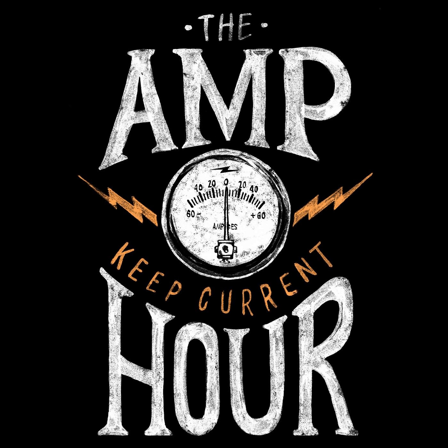Turbo pumps are definitely that level. That's what the turbo pump does. If you try to start a turbo pump up in atmosphere, it will not work. It only works when you've pulled a pretty good vacuum already. Interesting. Okay. The turbo pump is so finely balanced and so well engineered for operating at these high vacuum levels where there's barely any air molecules that if you try to run it in atmosphere, it will probably destroy itself, just because there's so much stuff that gets in the way.